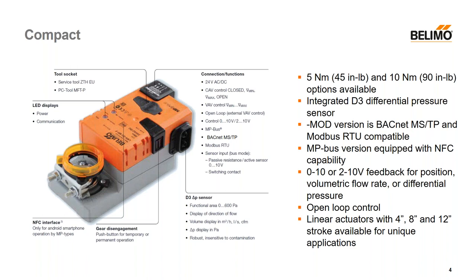We have a Dash Mod version available that is both BACnet MSTP and Modbus RTU compatible. We also have an MP bus version equipped with near field communication capability, which is really nice especially during commissioning. If you need to set your nominal flow rate or nominal pressure, you can do that with your cell phone rather than needing to connect to the actuator using PC tool. You can use either zero to 10 volt or two to 10 volt feedback, and this feedback can send a signal for actuator position, volumetric flow rate, or differential pressure.